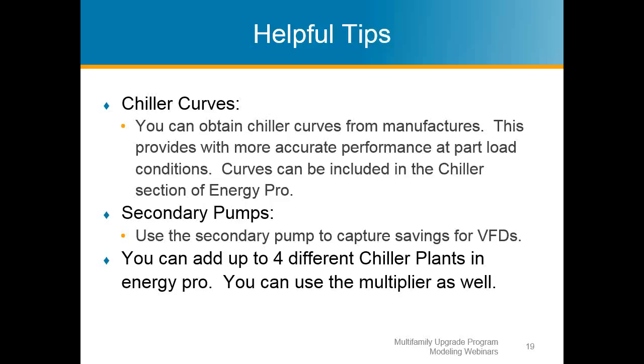The pumps thing, I bring this up again because it was one that I wrecked my head over for a while. I couldn't figure out how I could use the VFDs in the EnergyPro software, and then I came to find out you can use the secondary pump section to account for VFDs and plug that information in there. Again, if you go out and you see just a constant running pump, or a two-stage pump or something that's just on and off, VFDs, man, they save people a lot of money. Even pool pumps. If you're dealing with savings for pool pumps, VFDs, changing those out to get more efficient savings, is always the option to go for, in my opinion.